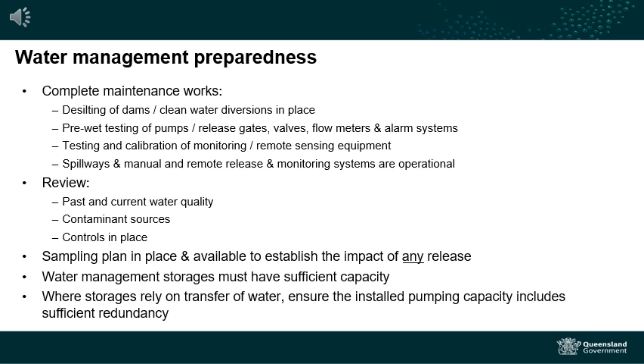Pre-wet season testing should be undertaken on pumps, release gates, valves, flow meters or other systems used in the operation. Testing and calibrating monitoring equipment and remote sensing equipment prior to the wet season will ensure they operate smoothly at short notice and any recorded results can be relied upon. Making sure everything is working smoothly prior to the forecasted weather event is important to meet your general environmental duty. For larger sites with regulated structures and spillways, make sure that all their water management systems are operational.